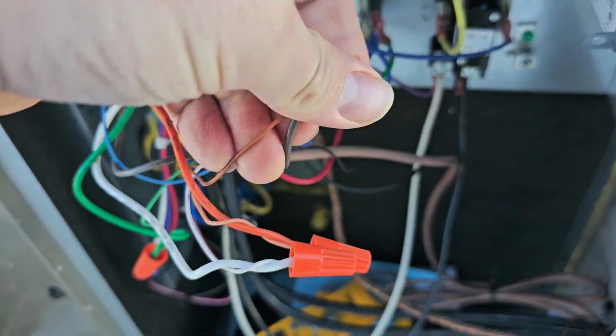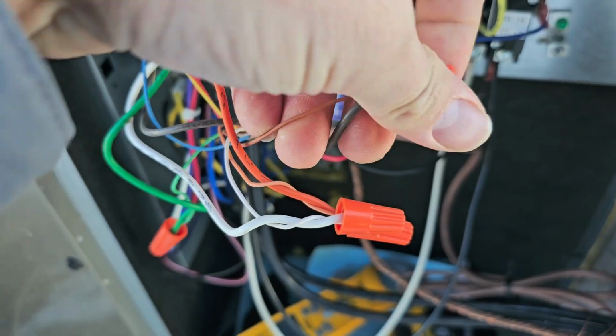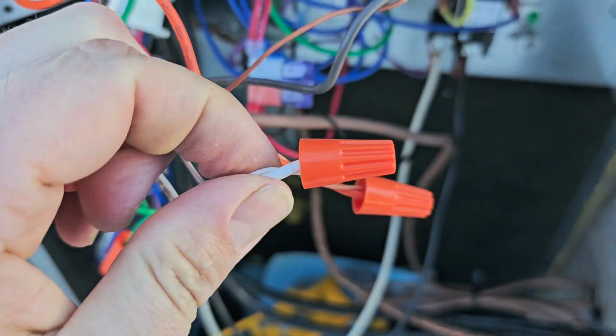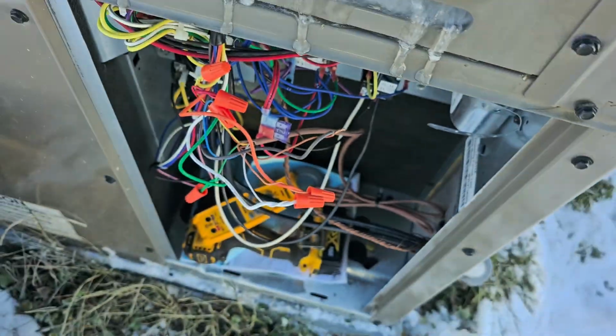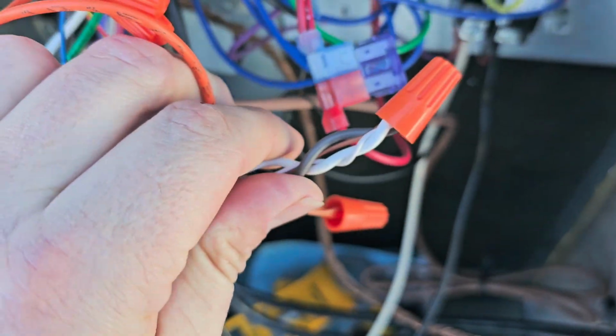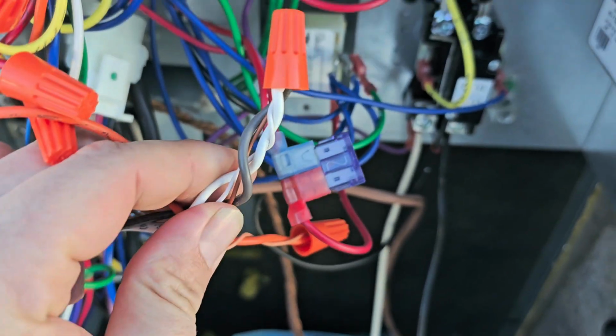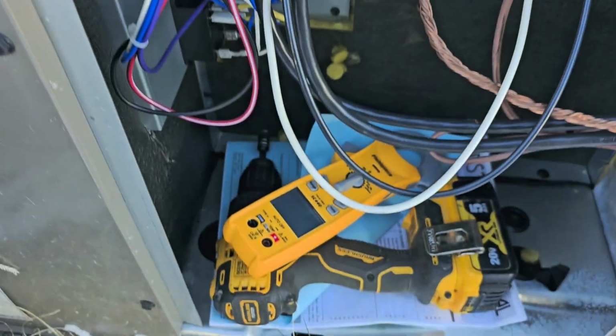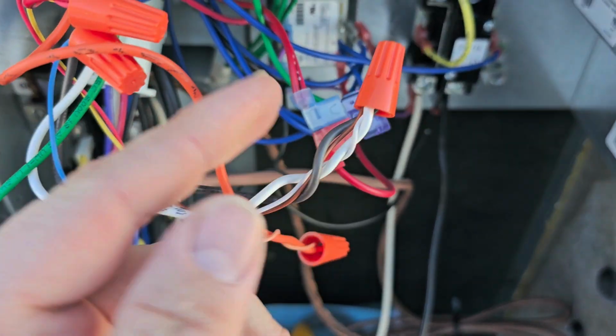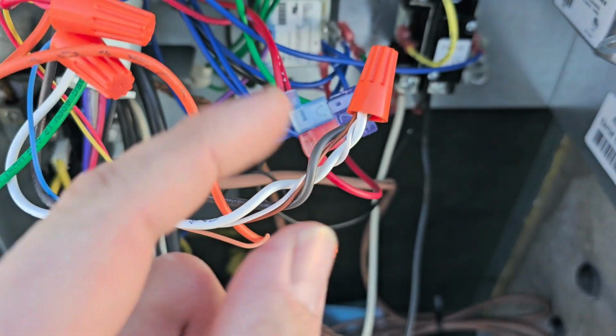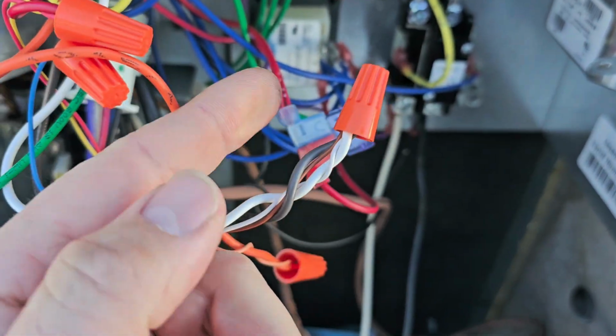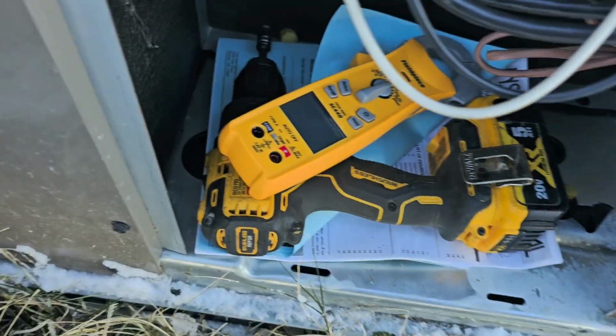I just need to take this brown wire, and I can actually just put this under the same terminal as the white, and that should engage my heat strips. I'm gonna do that real quick. All right, so I got the white and the brown connected. So now whenever it engages auxiliary, it'll engage that white wire. Whenever it turns on the emergency heat, it'll engage that white wire.